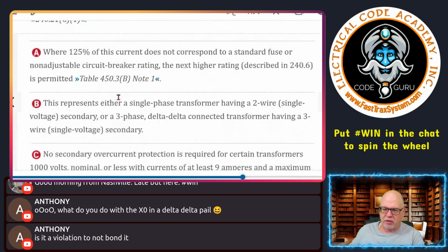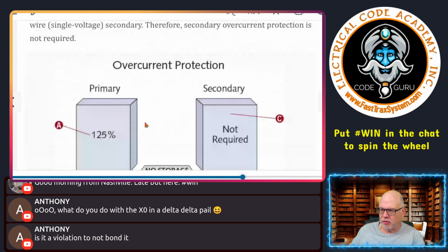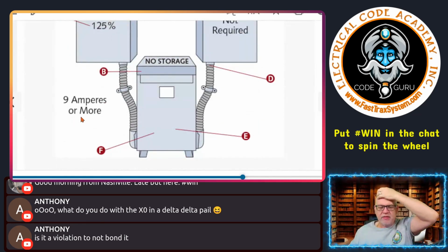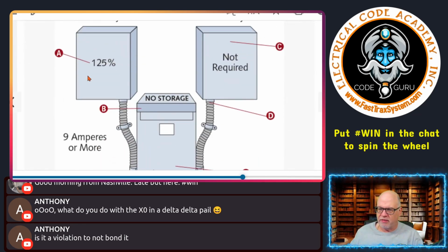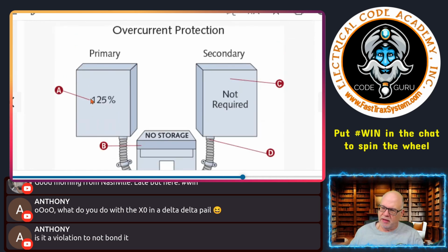So let's get into what we would normally see. Let's go, if we've got an image here. It's 9 amps or more. This is your typical installation, where you have primary overcurrent protection, and whether or not secondary overcurrent protection is required. One thing to remember is that even where we look at the tables, secondary protection of the transformer may not be required. However, if this is supplying a panelboard, then there are rules in 408.36 and things like that that require us to protect that panelboard.